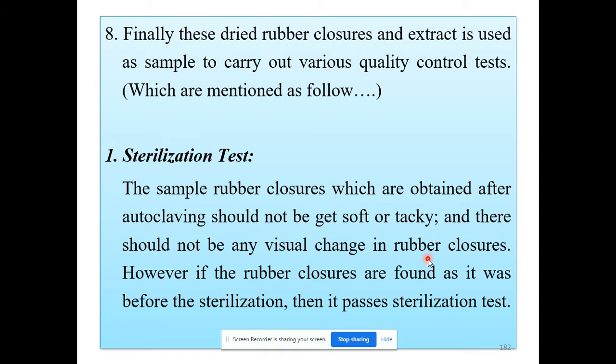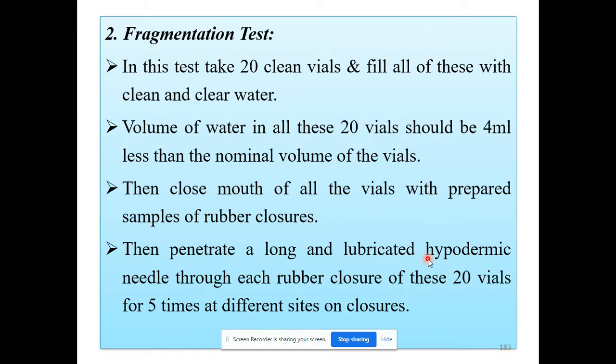After autoclaving, rubber closures should not be soft or sticky, and there should not be any kind of visual change in the rubber closure. If the rubber closure is able to withstand the high temperature and pressure of autoclaving, it passes the first quality control test — the sterilization test.